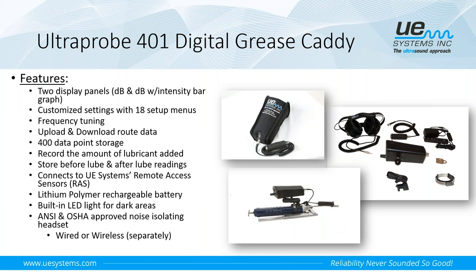You can store as many as 400 points of data. So we can create a route of up to 400 points, load that route from the software into the grease caddy. If you have more than 400 points, it would be necessary to break those up into smaller routes. Typically, we'll teach that for good data management and ease of data collection, no more than about 150 points per route. Now, the good thing in the software is you can have a significant number of routes created underneath the same plant, underneath the same application.